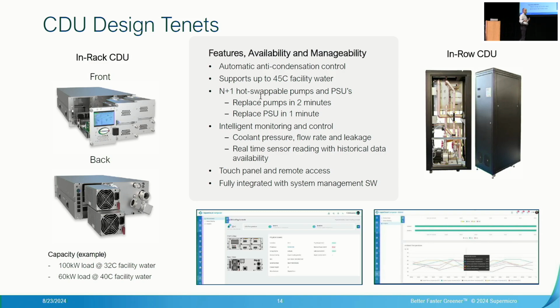One interesting thing about direct liquid cooling versus traditional air-cooled data centers: with air cooling you send water out to a cooling tower and it comes back in cold. With direct liquid cooling, that water doesn't have to come back in at such a cold temperature, so you don't have to spray water on it as often, meaning you don't waste as much water.